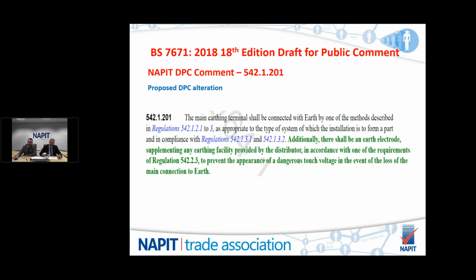And the next one we have is Regulation 542.1.201. This is an existing regulation and it has an additional wording added to it. As it states there in the green, additionally, there shall be an earth electrode supplementing any earthing facility provided by the distributor in accordance with one of the requirements of Regulation 542.2.3 to prevent the appearance of a dangerous touch voltage in the event of a loss of the main connection to earth.